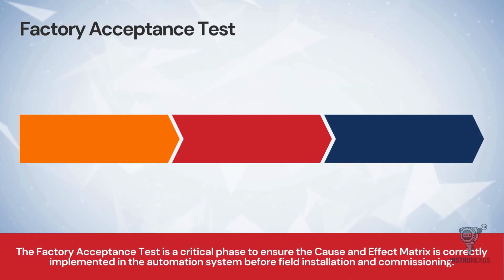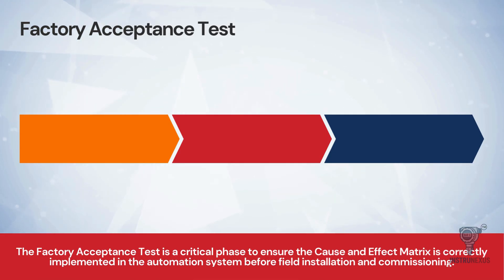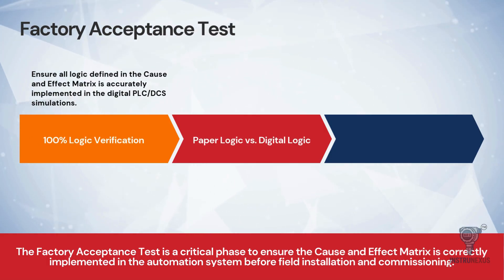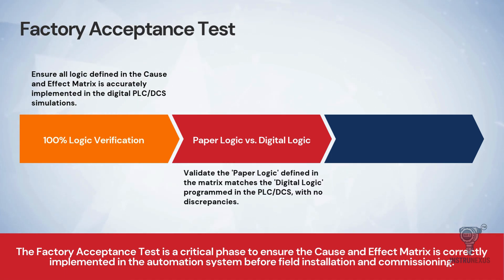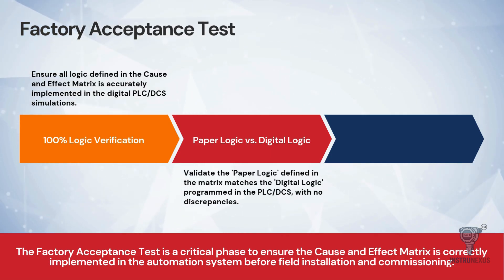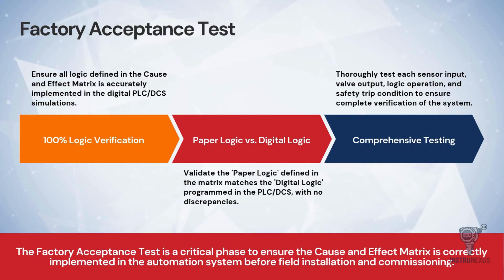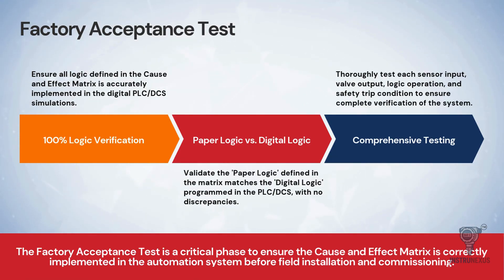Before the system ever touches the plant floor, it undergoes a factory acceptance test, or FAT. This is a comprehensive simulation environment, and the goal is 100% logic verification. We are comparing the paper logic — the cause and effect matrix we just wrote — against the digital logic running inside the PLC simulation. We trigger every single virtual sensor and watch the virtual valve's response to ensure there are absolutely no discrepancies. We test every input, every output and every trip condition. Any error found here is logged, fixed in the code and retested to ensure the digital brain matches the engineering blueprint.